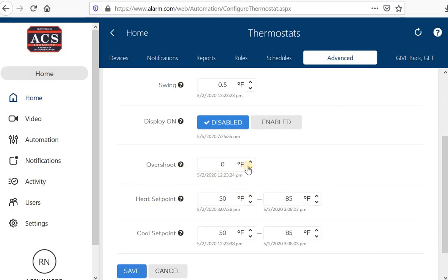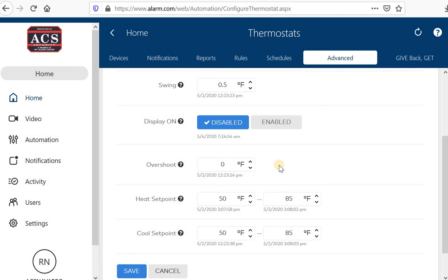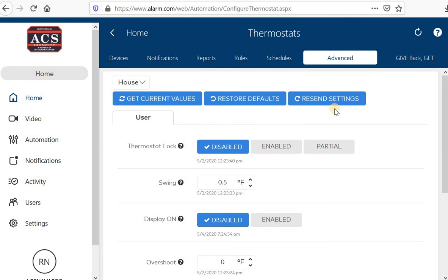If overshoot, that would be if the system is trying to cool the house and you have it set and your desired temperature of 70 degrees at zero, it'll stop. Air conditioning will stop once it hits 70 degrees. If you want to overshoot by one degree or two degree, it'll overshoot that, meaning air conditioning will run until it gets to 69 if you have it at one degree, and then go ahead and shut off. Heat set point, cool set point is the maximum and minimum. Those are the advanced rules.